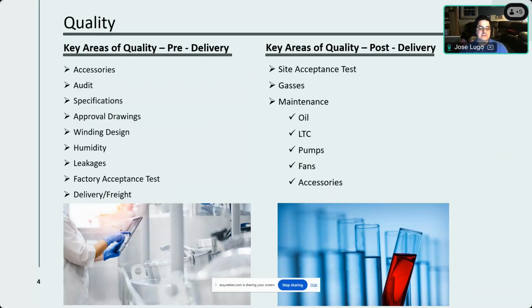And then there's humidity. Humidity is another enemy of a power transformer. If you have humidity inside of a paper type device, it will have issues. Leakages. This thing is surrounded by oil in a tank. Everything has to be sealed. And a quality of a power transformer is that you'll have zero leaks. And you actually test this in a facility and when it arrives, to make sure that during delivery nothing happened at that point.